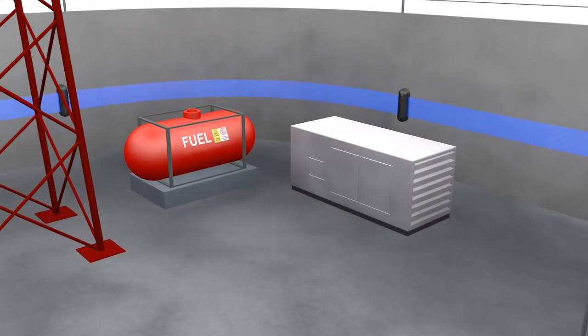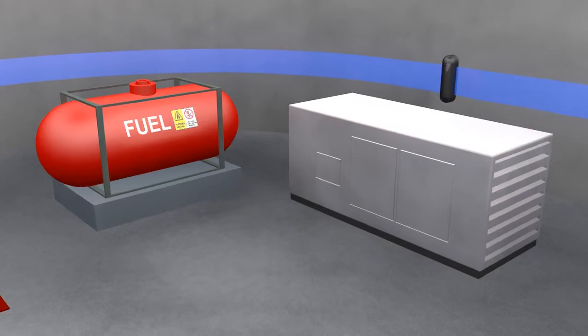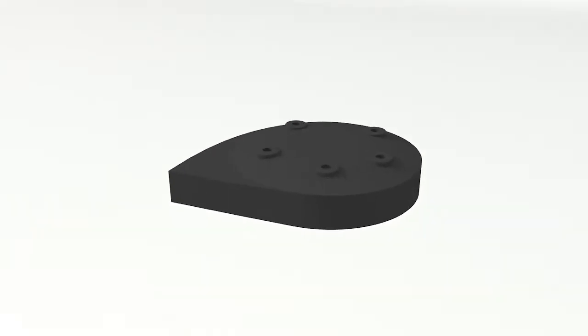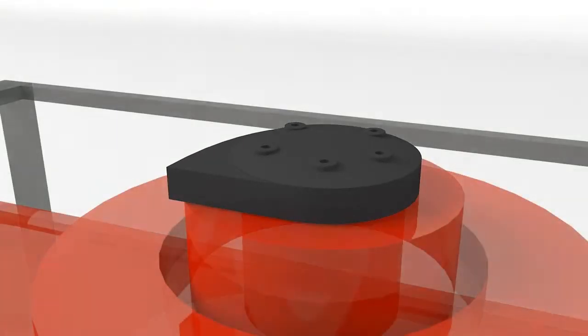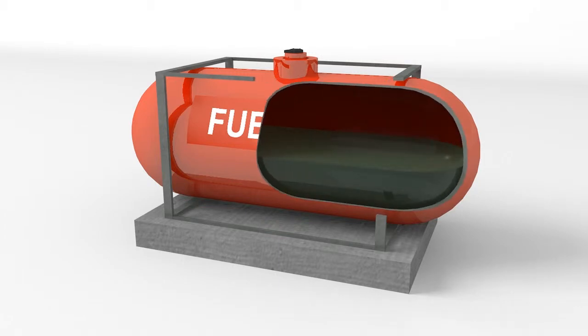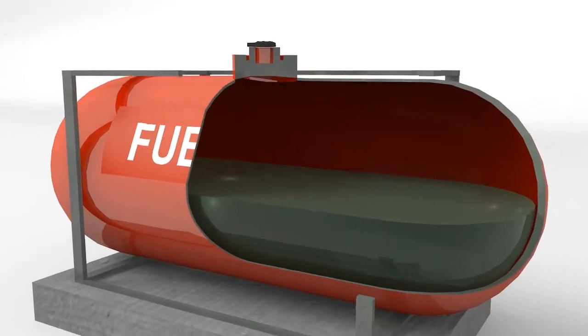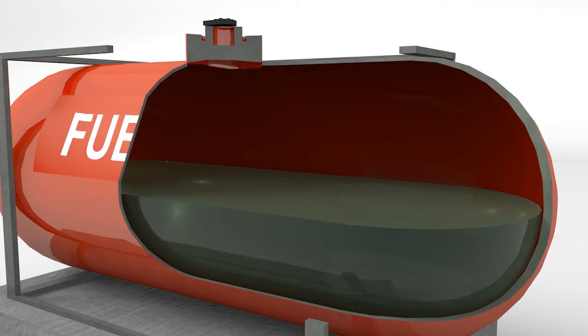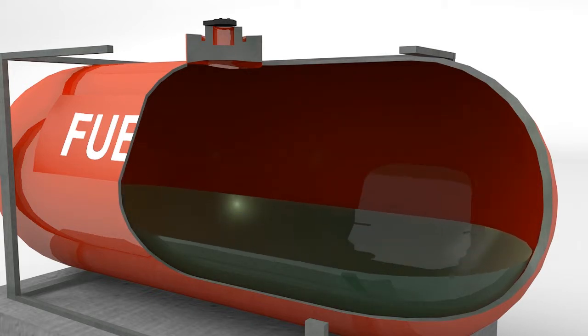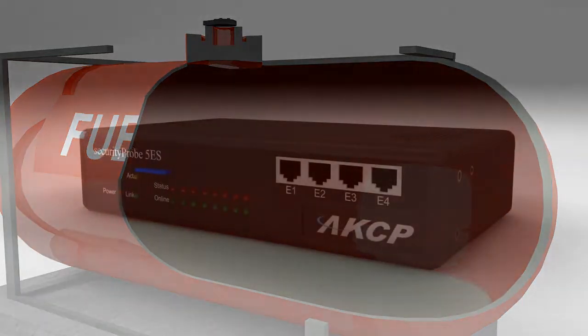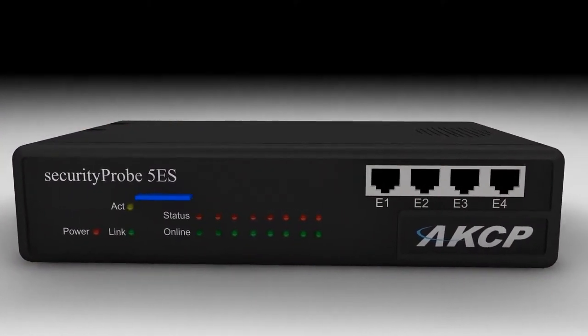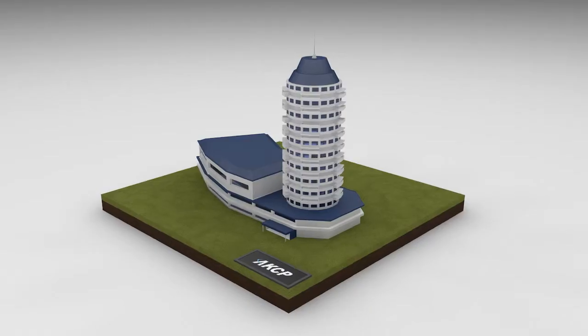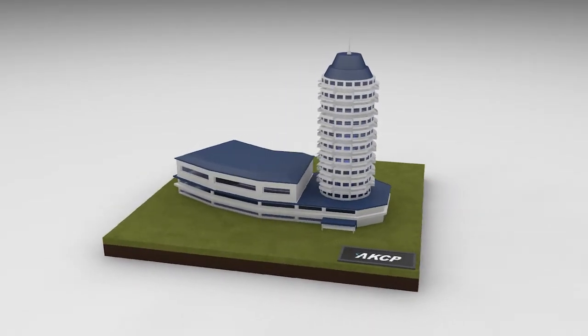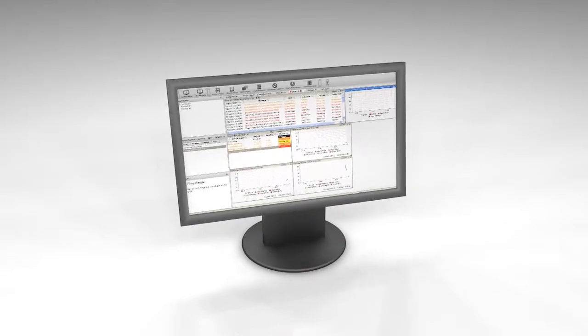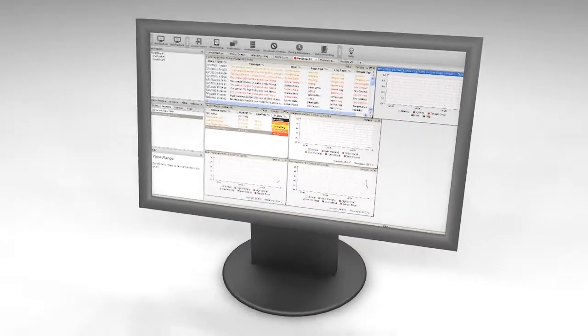Backup generators need an on-site fuel supply. This can also be monitored. The ultrasonic fuel sensor has been designed to monitor fuel usage from exterior storage tanks. This modern fuel sensor works by sending ultrasonic signals to the surface of the liquid. As the liquid drains, the signals take longer to return to the sensor. This information is then displayed within the security probe base unit. All data can then be monitored from your main monitoring station using AKCP's AKCess Pro server software.